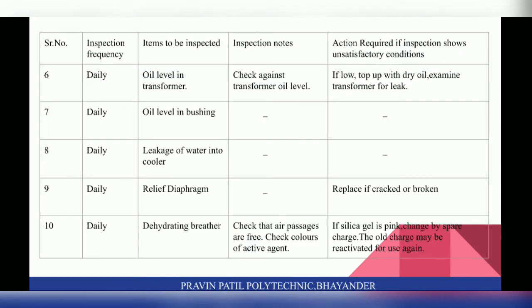On a daily basis, check the oil level in the transformer. If the level is low, top up with dry oil and examine the transformer for leakage. Also check oil level in the bushing, leakage of water into the cooler, and the relief diaphragm — if the diaphragm is cracked, replace it. Check the dehydrating breather: ensure air passages are free and check the colour of silica gel. If silica gel is pink, change it with a spare charge.